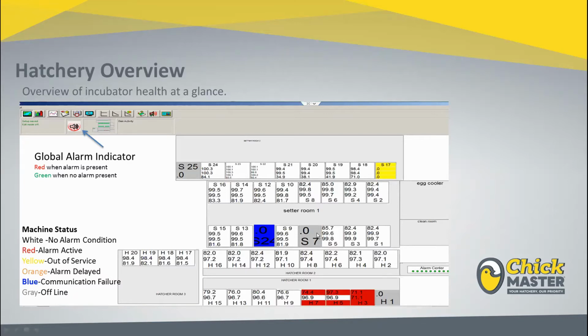A gray machine, like you see here, is an indication of a machine that's been taken offline. You take machines offline when you're performing tasks on a machine, for example, if you want to take the power completely away from a machine for some reason, so it would lose communications. But if you take the system offline, Maestro isn't continually polling, and it will also not cause an alarm for a comm failure when it's in the offline state. I don't have a sample of an orange machine here, but if an alarm is silenced or delayed at the machine, then the machine turns orange to indicate it.